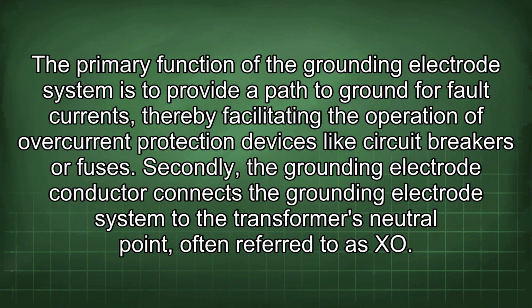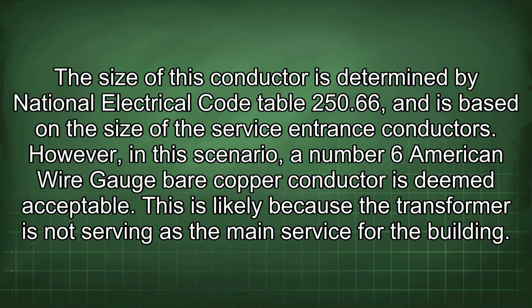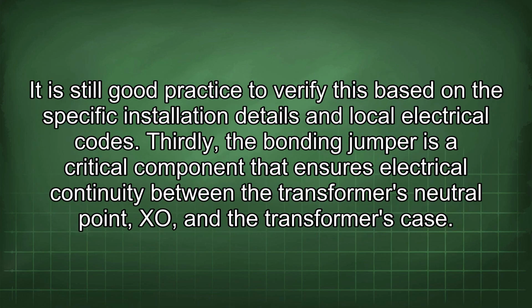Secondly, the grounding electrode conductor connects the grounding electrode system to the transformer's neutral point, often referred to as XO. The size of this conductor is determined by National Electrical Code Table 250.66 and is based on the size of the service entrance conductors. However, in this scenario, a number 6 American wire gauge bare copper conductor is deemed acceptable. This is likely because the transformer is not serving as the main service for the building. It is still good practice to verify this based on the specific installation details and local electrical codes.